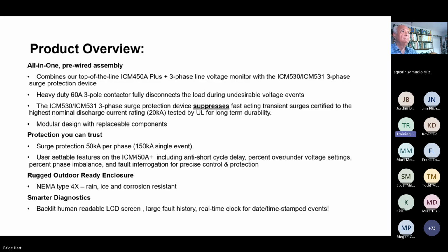And what I mean by surge suppress is if we clamp that voltage, that surge, we dissipate the surge as heat throughout the device, and these are thermally protected so that the surge suppressor can take itself out of the circuit if it has been exhausted, without sitting there and just cooking if it didn't have that thermal protection. This is a modular design, so if the 530 or the 450A or any of the parts break down, you can easily take out and replace those devices individually. So modular design with replacement components.